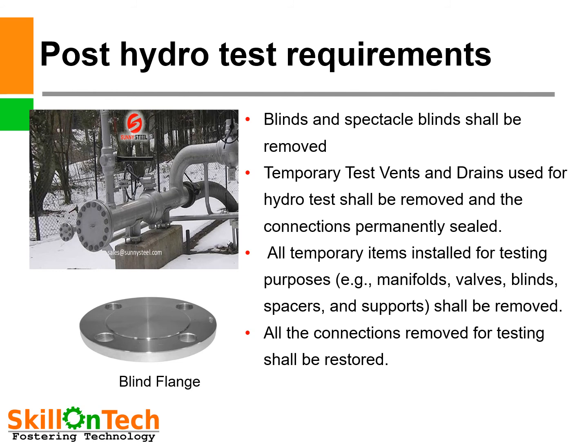Blinds and spectacle blinds shall be removed. Temporary test vents and drains used for hydrotest shall be removed and the connections permanently sealed. All temporary items installed for testing purposes, such as manifolds, valves, blinds, spacers, and supports shall be removed. All the connections removed for testing shall be restored.